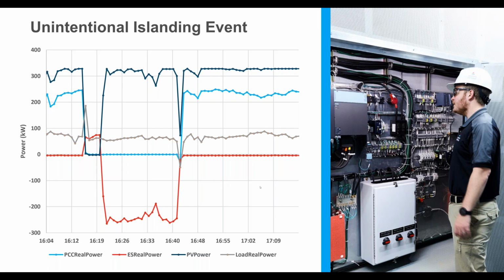So to now go into the details of how this happened, I'll just explain what this chart in front of you depicts. The blue line is the power control center real power. That is the real power being provided by the grid. The red line is the energy storage real power. The black line is the photovoltaic, the solar real power. And the gray is the load real power. What you see here is when the PCC real power dropped offline, that's when the main grid was disconnected. The solar dropped off as well, and that's because of the transient introduced by the drastic opening of the recloser.